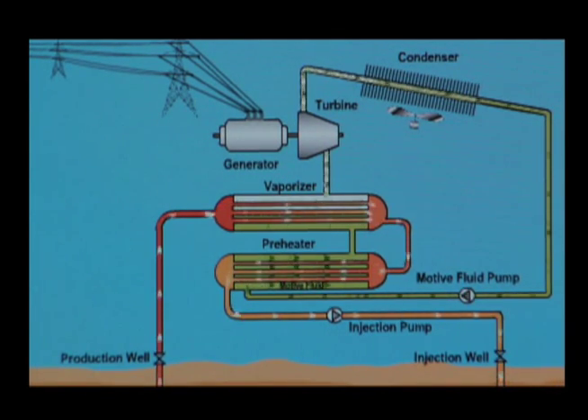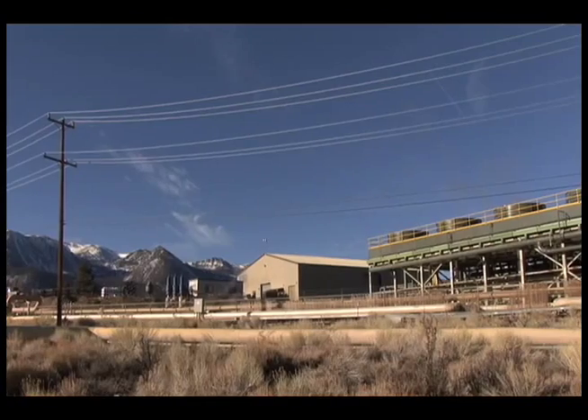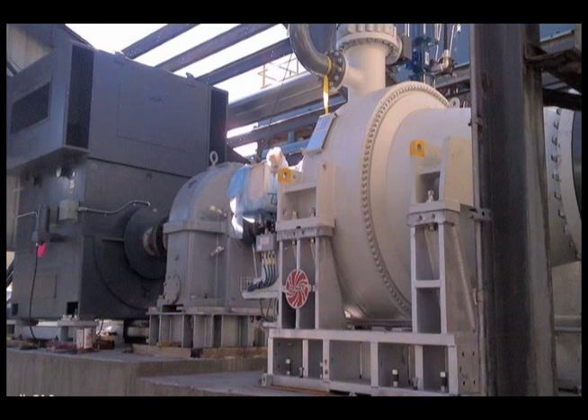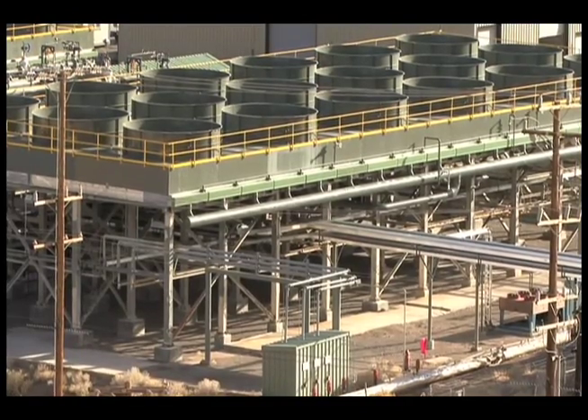On the other side — the binary side — the second fluid is a motive fluid internal to the process that runs like a refrigerant cycle in reverse, where that heat vaporizes this fluid, it runs a turbine or series of turbines, gets cooled back down through a set of air condensers, and pumped back through as the cycle continues.